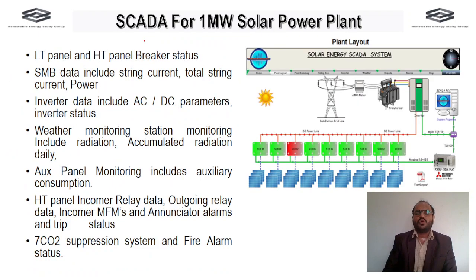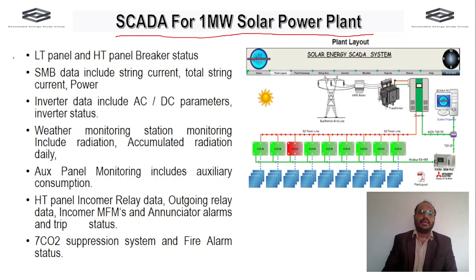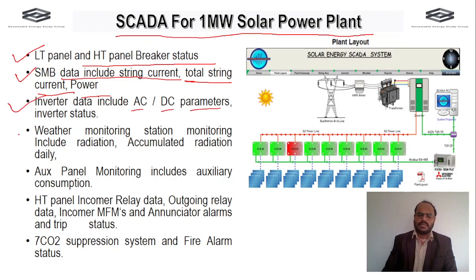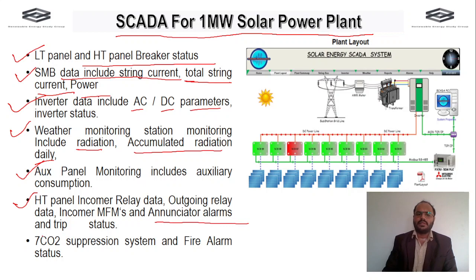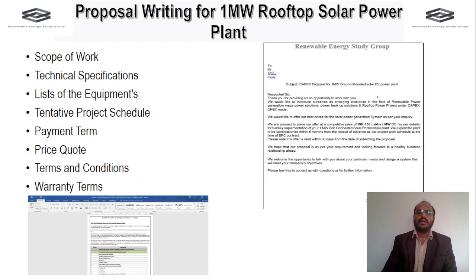We also cover the SCADA system for a one megawatt solar power plant — its major functionalities and parameters to be monitored. These include LT and HT panel breaker status, solar monitoring box data such as string current and total string current, inverter AC and DC parameters, inverter status, weather monitoring station data including radiation and accumulated daily radiation, auxiliary panel monitoring, auxiliary consumption, HT panel incomer and outgoing relay data, incomer MFMs, annunciator alarms, trip status, CO2 suppression, and fire alarm status.